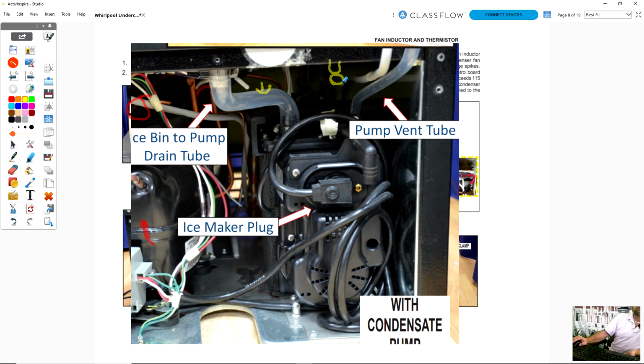Why? Because the older condensate pumps would plug right into the bottom of the ice maker, and if it was plugged into the bottom of the ice maker and you removed that bypass there, what would happen is there is a safety switch here. If your condensate pump fails to pump out, let's just say the condensate pump builds up algae, the pump's running but the water's not going out, well, the next thing is that pump's going to overflow with water and it's going to be all over the place. So they put a safety float switch in there that will shut the ice maker off and not allow the ice maker to run until this is emptied out.